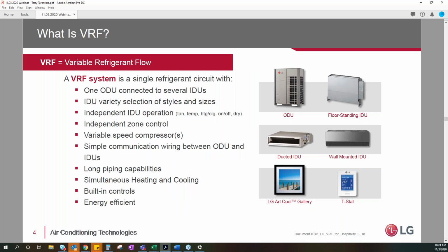VRF system, it's a single refrigerant circuit that we can connect multiple units to. And this goes as well for water source heat pumps. A lot of them share some similar characteristics. We get zoning. Both systems lend themselves to zoning extremely well. One advantage VRF has is we have a number of options on what we put inside the room.